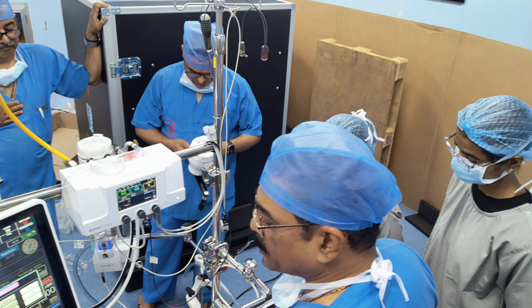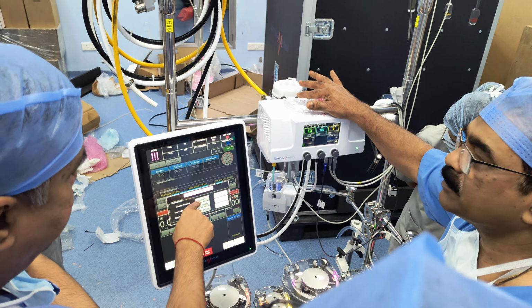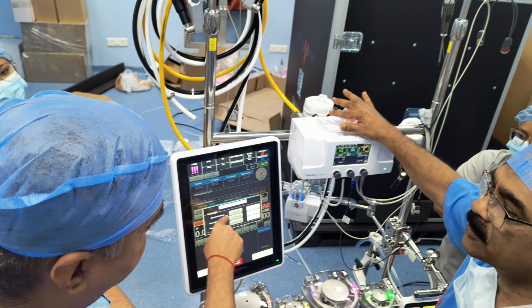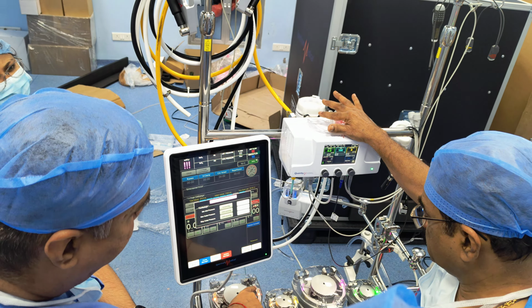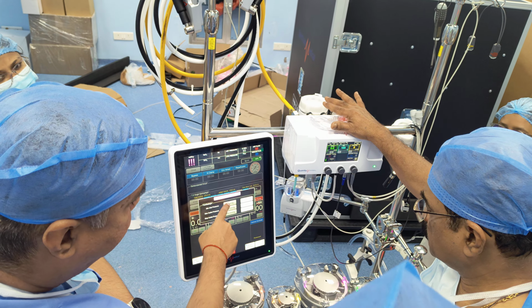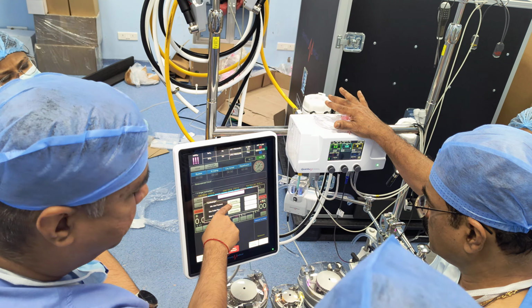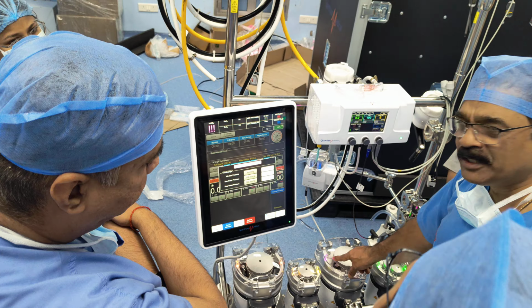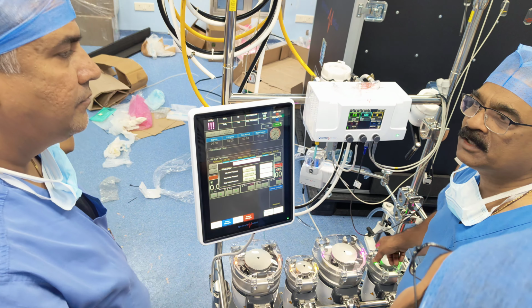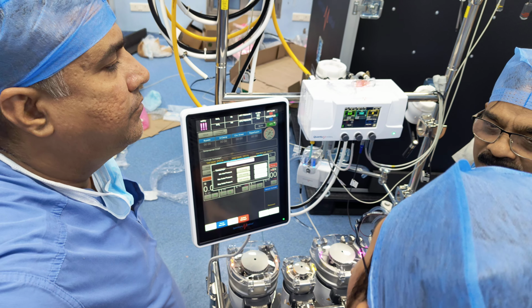This pump pressure, your arterial pump, cardioplegia pump. Let me understand what I understand from your voice. This 5 mm pressure you have given, when your cardioplegia occlusion will be tightened, will the pressure generate with this? No. This is linked to your arterial line pressure. Okay, arterial line only. Because you are taking blood from the arterial line for your cardioplegia pump. If the arterial pump is stopped, then it will automatically stop.